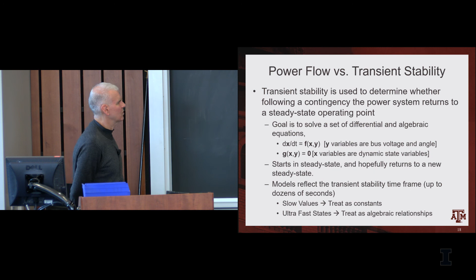What I'm going to show you in the next visualization is how a power grid would respond to the loss of generation. This is a graph showing the system frequency. Usually the frequency of the grid is around 60 hertz. When a generator fails, we lose some generation. So as you lose generation, the system starts to decelerate. It starts to slow down. As it slows down, the frequency drops.